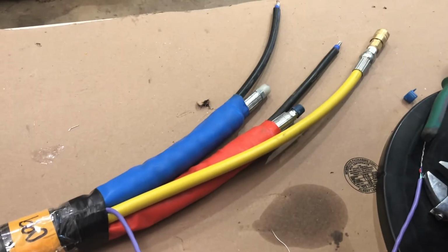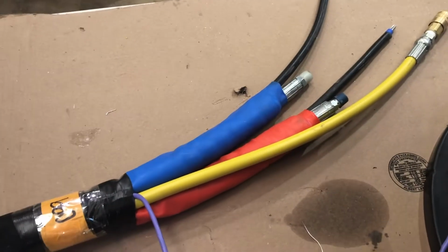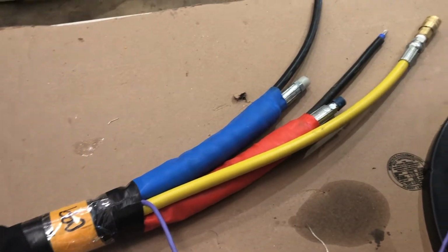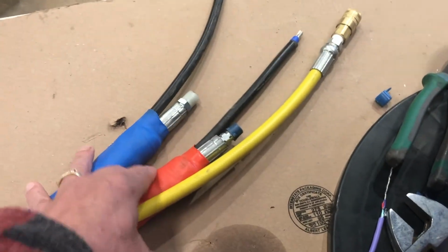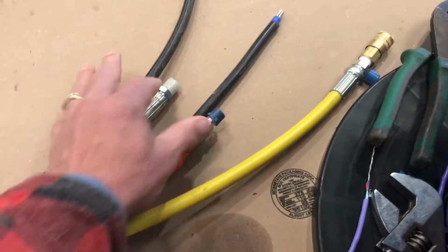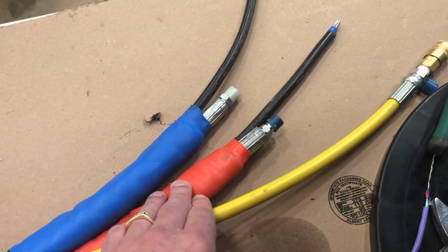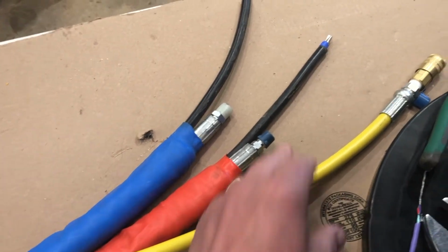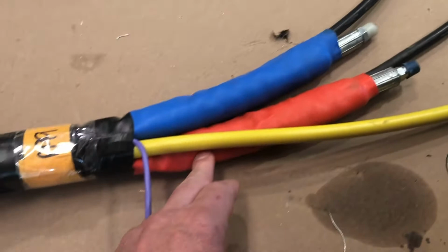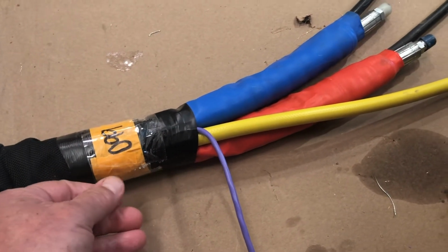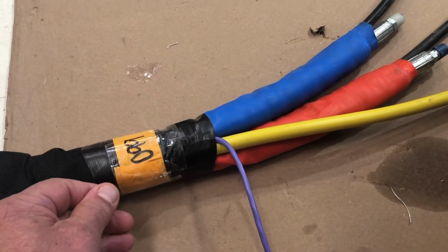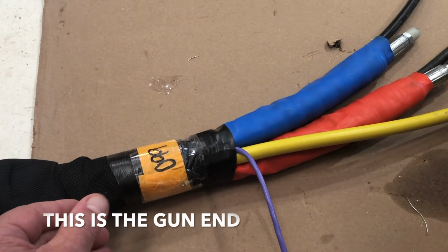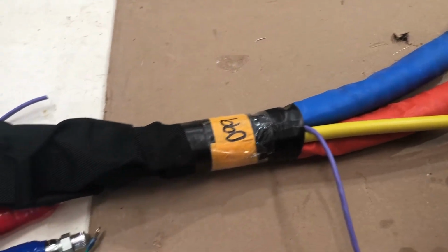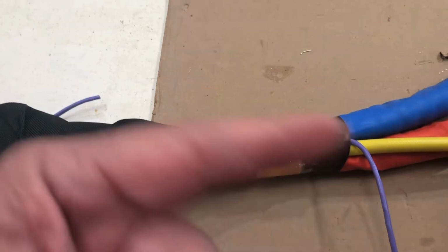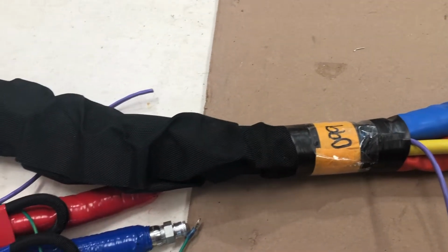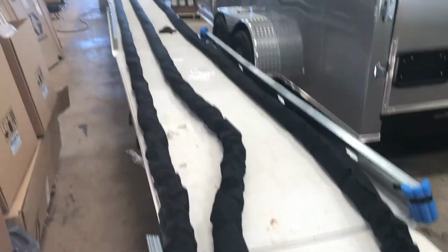So these hoses are 50 feet long. They are heated, and here's your main hoses, your fluid hoses. We're at the male end. You got your A side and your B side. These 6-gauge wires come up inside here and are soldered to about a 1/4 inch wide flat copper wire that wraps around the hose all the way to the other end.